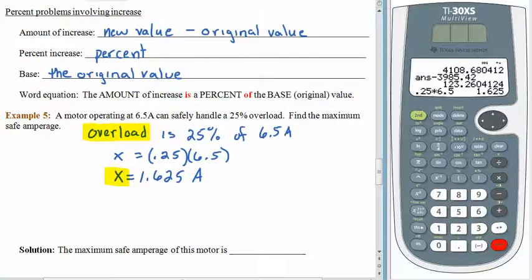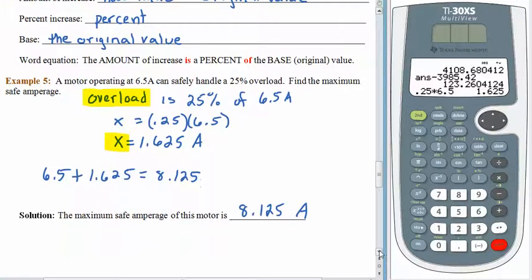The maximum safe amperage is not 1.625 amps. Right? It can already operate at 6.5. So the maximum has got to be bigger than that. We, of course, need to take the overload and add it to the 6.5. So we have 6.5 plus 1.625. And that's 8.125. So periodically this motor can handle 8.125 amps if it needs to. Alright. On to the next page. We're almost done. Hopefully you're seeing and feeling that these problems are all the same because they are. We just have to read carefully.